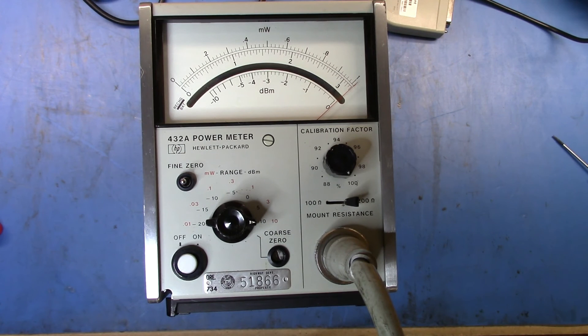What I can do is either buy another 478A mount and then sell this, or I'm going to have to send it off to Keysight and have the mount calibrated. Otherwise, I'm going to have to try and calibrate it myself, and I don't think I have anything that can actually calibrate the frequency stuff properly, or at least to the 0.5 percent specification that is possible to get out of this meter. Anyway, I hope you found that interesting. Catch you later, bye.